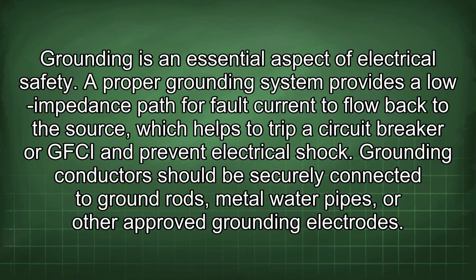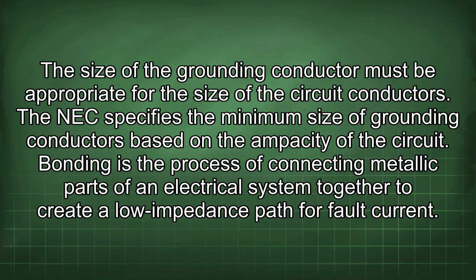Grounding conductors should be securely connected to ground rods, metal water pipes, or other approved grounding electrodes. The size of the grounding conductor must be appropriate for the size of the circuit conductors. The NEC specifies the minimum size of grounding conductors based on the ampacity of the circuit.